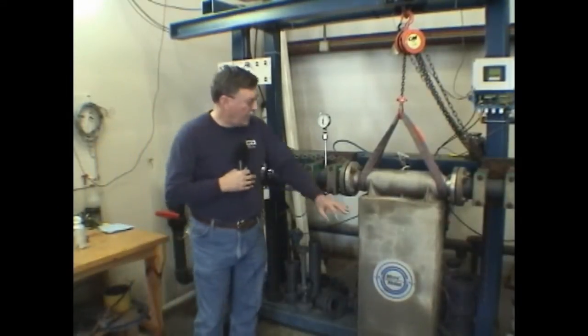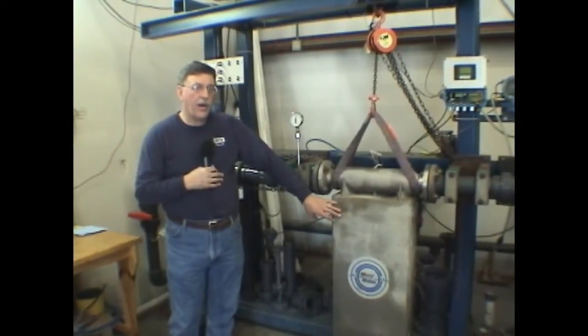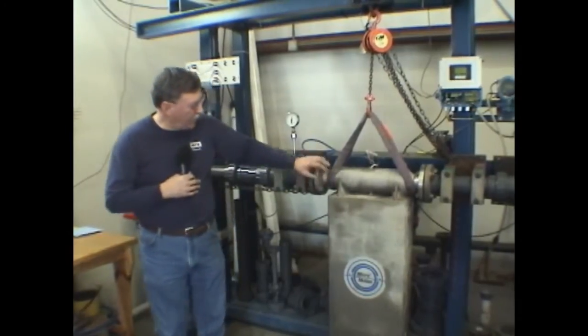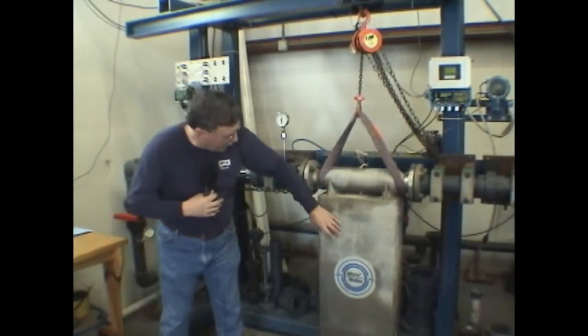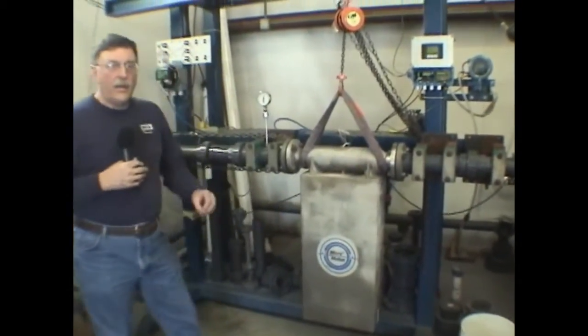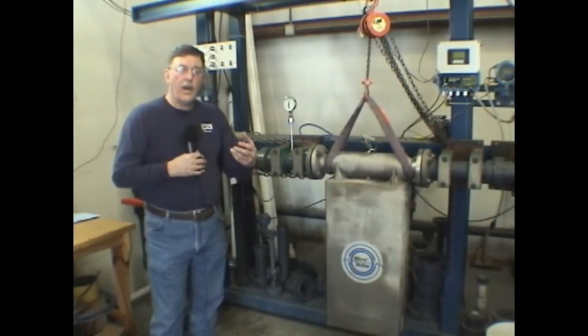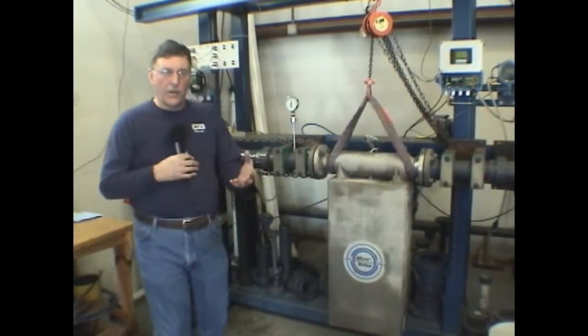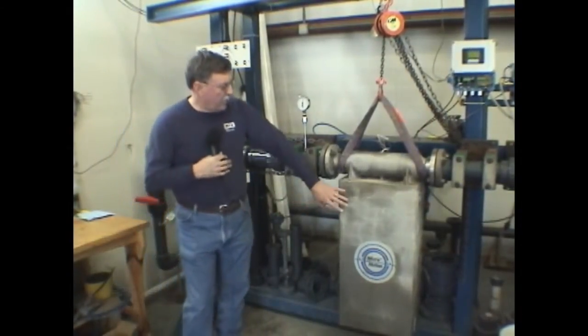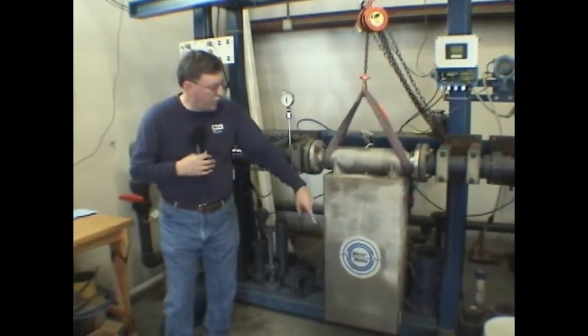Some meters, the Coriolis in particular, some of the designs have an elongated tube. In this case, the flow is diverted into two tubes that take a U shape. Now, the positioning of the tube is important here relative to the properties of our process. If we're going to be measuring a liquid process, we always want to install this type of flow meter so that the tubes are down. Therefore, gravity will keep the tubes full of liquid.